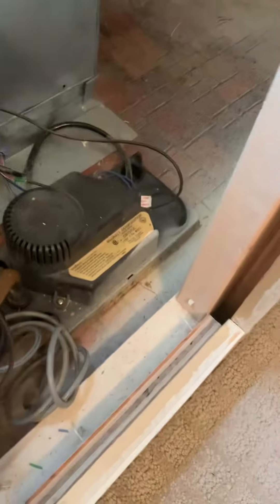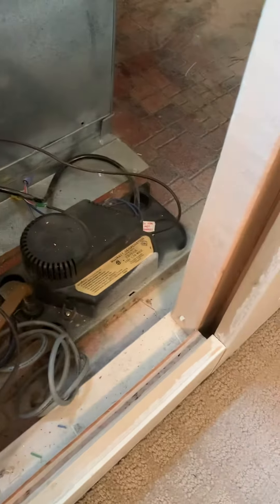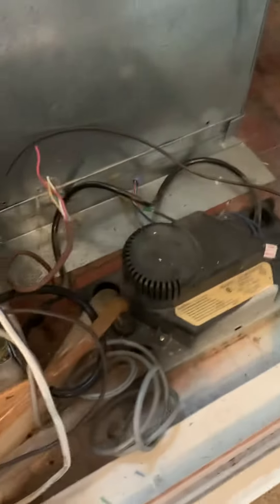The condensate pump is actually sitting inside of the flooring — it's cut out and it's just rusting in there. So we can look at bringing in a new pump, but we may end up reusing the same one and modifying our drains so we're just coming back catching right here with our PVC.